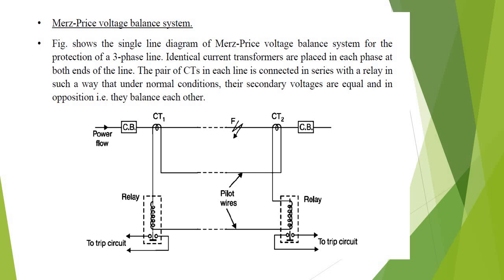Suppose there is a fault occurring at point F1. This will cause a greater current to flow through CT1 than CT2. Consequently, their secondary voltages become unequal and a circulating current flows through the pilot wires and the relay. The circuit breakers at both ends of the line will then trip and the faulty line will be isolated.